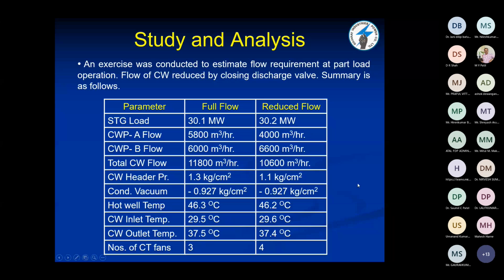Now we have carried out one study. An exercise was conducted to estimate flow requirement at part load operation. So first of all, we have to estimate the flow requirement at the part load: how much flow we can divert to the condenser to cater that requirement. The flow of cooling water was reduced by closing the discharge valve.